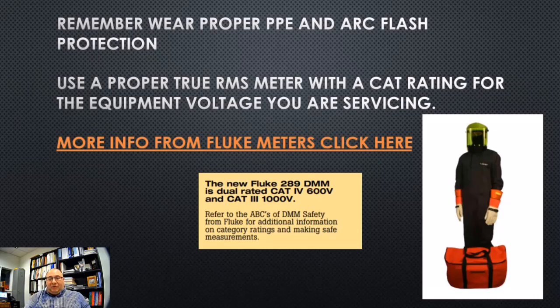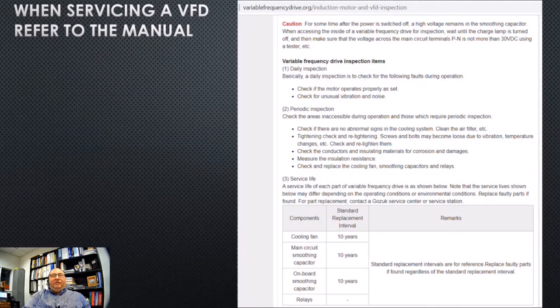this PowerPoint presentation in a PDF format. When servicing a VFD, it's always good to refer to the manual. There are some cautions that we have to take into consideration. And I'm just going to read this verbatim. For some time after the power is switched off, high voltage remains in the smoothing capacitor. We also call that the DC bus.